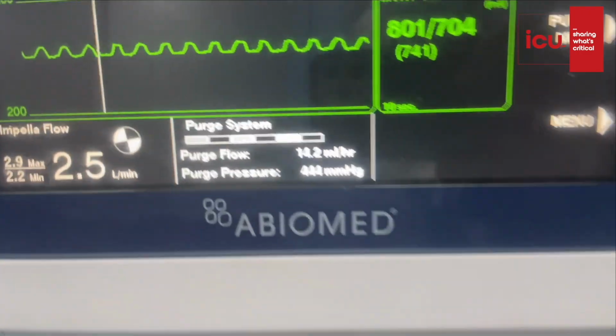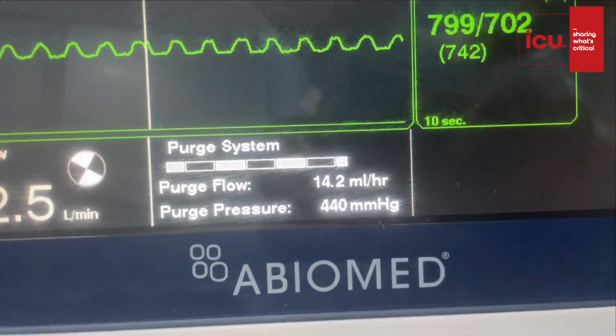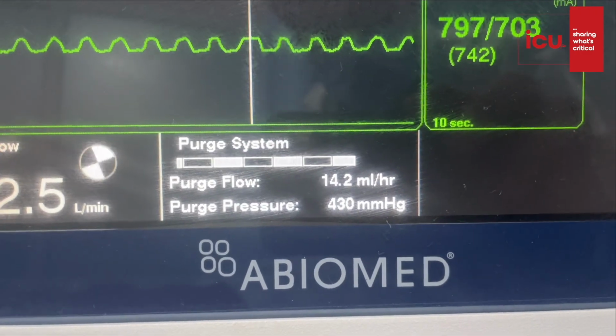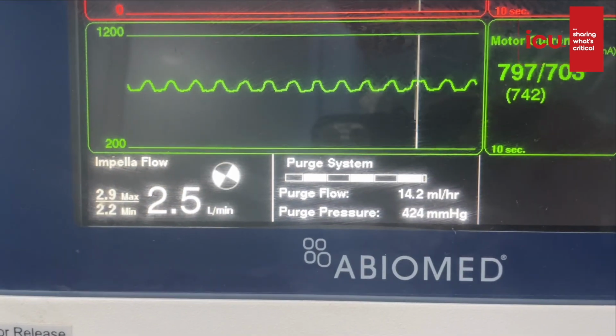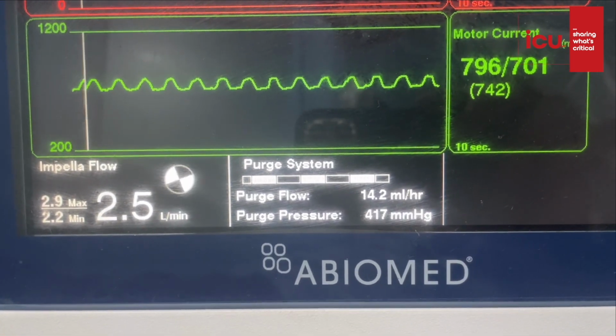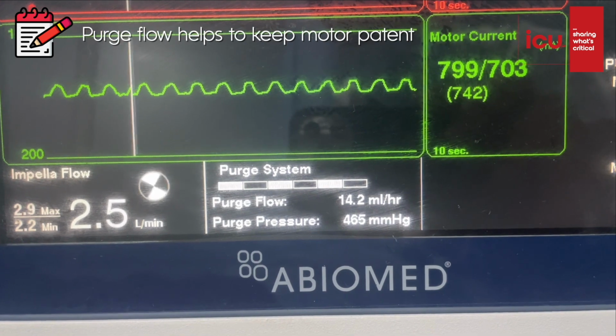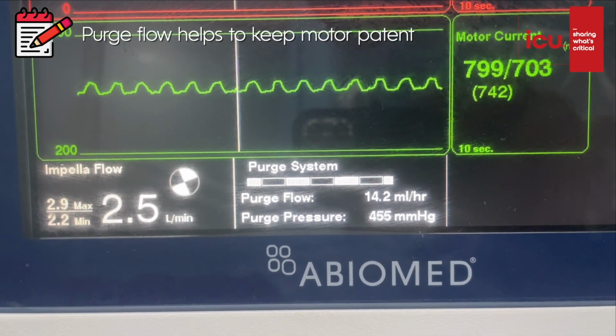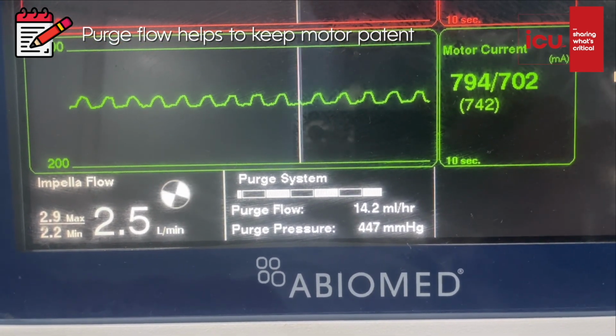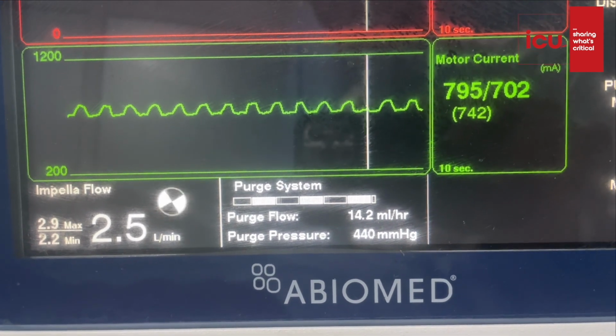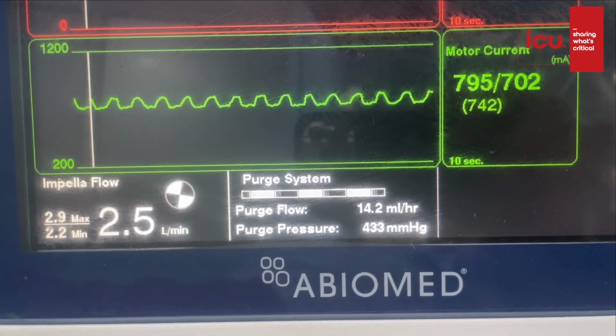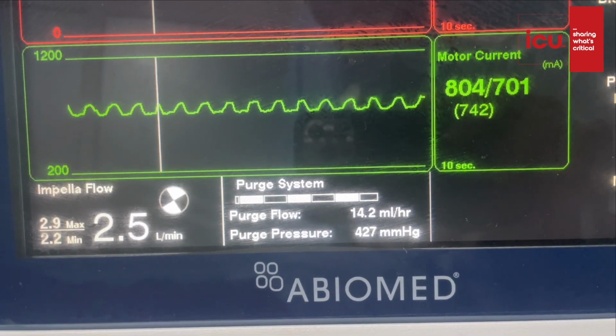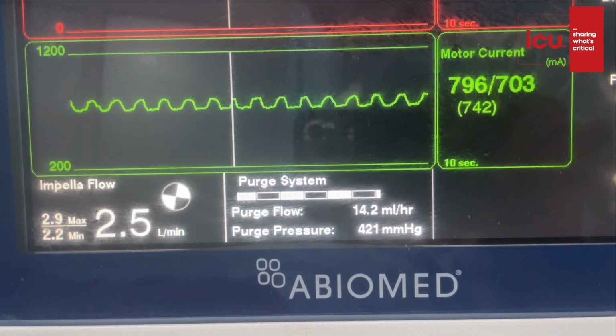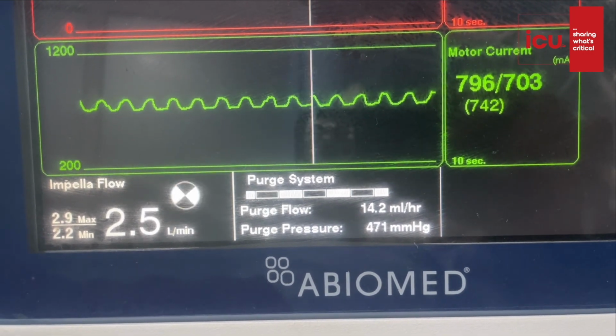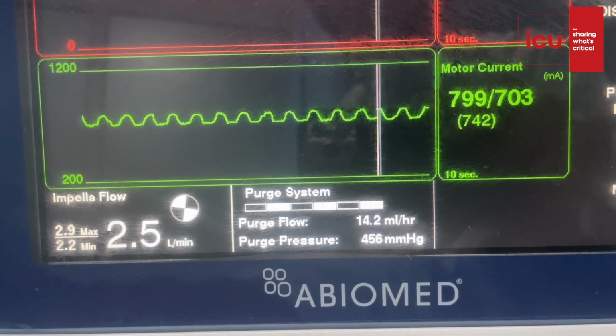Now there is a purge pressure and the purge flow that you can see, and both of these can be determined automatically by the system. So you don't have to manually adjust this. The purge flow range is anything between 2.5 to 30 ml per hour, and we always use dextrose in the purge. We never use sodium chloride. Dextrose can be used at either 5%, 10% or up to 20%.